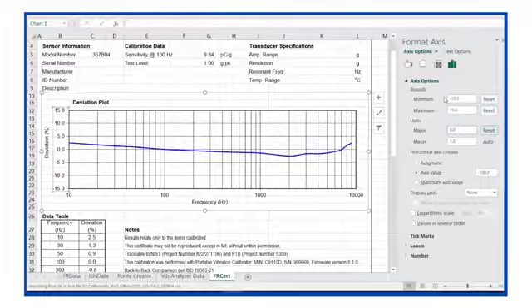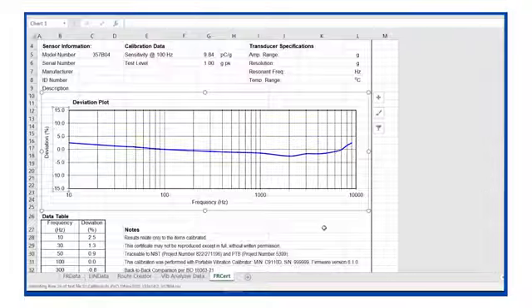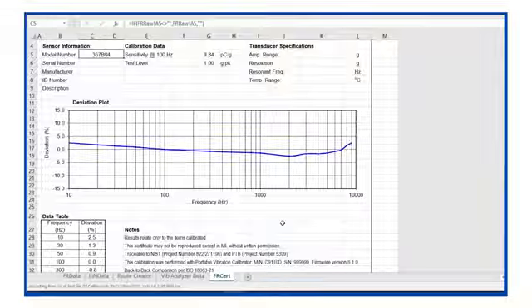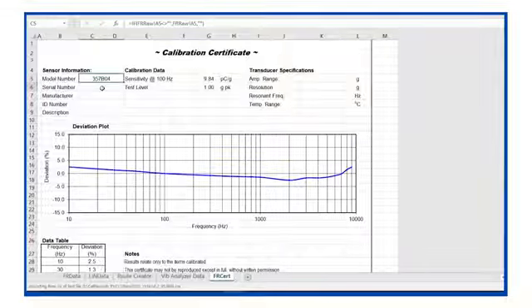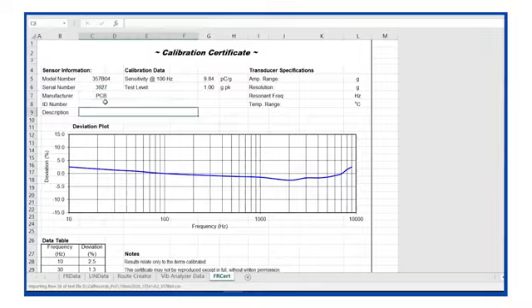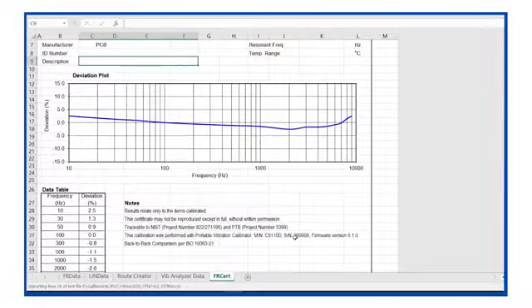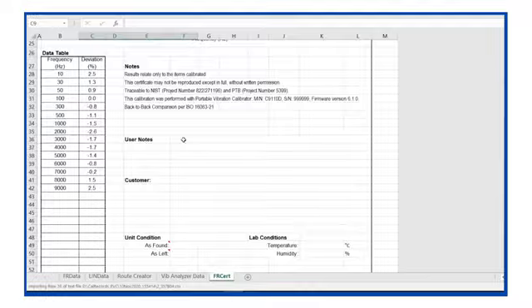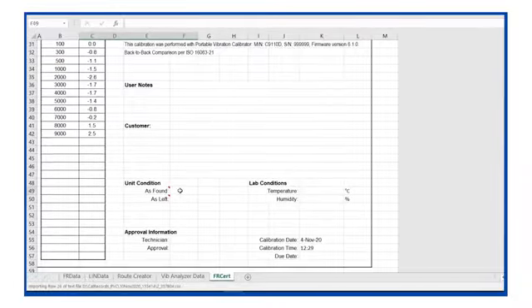Your calibration certificate looks really flat. Although again, I didn't change any data. I just changed the deviation scale over here on the y-axis to plus or minus 15%. From here I can enter the serial number, 3927, manufacturer PCB. I could enter a description of the accelerometer if I wanted, its specifications. I'll go ahead and skip that. You see the notes here, ISO 16063 part 21. I can enter anything I'd like for user notes, customer notes.